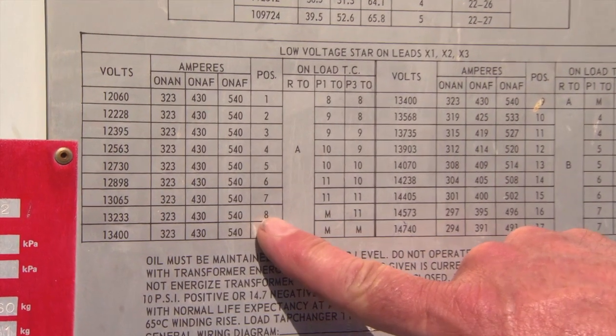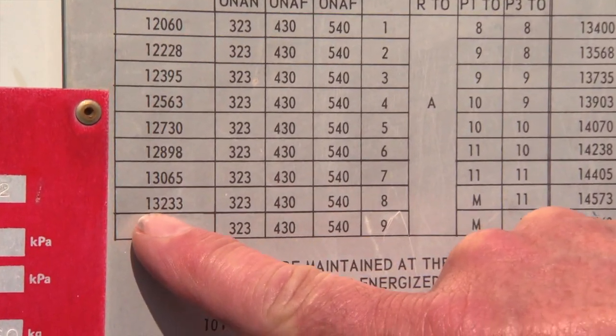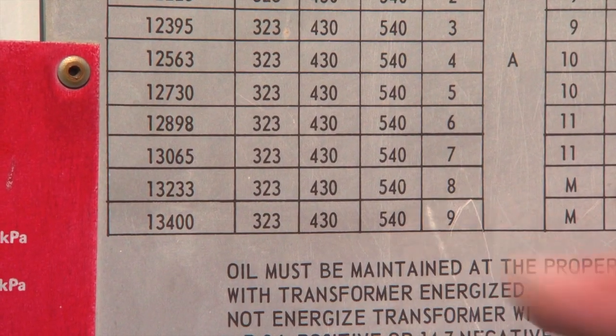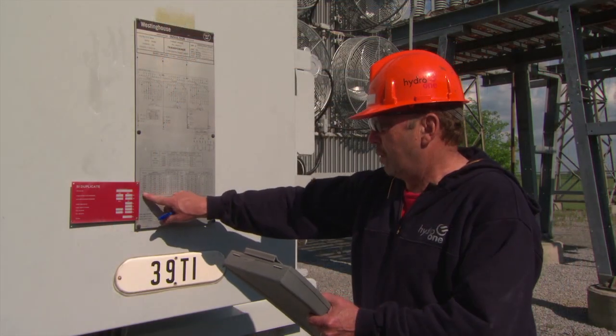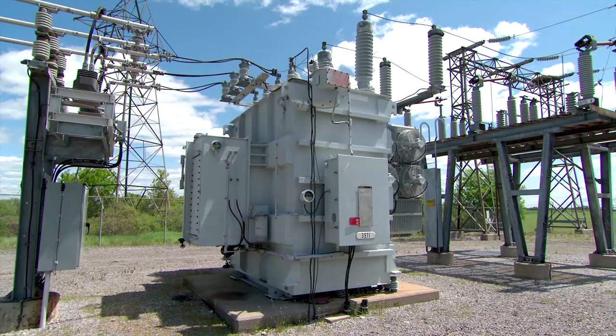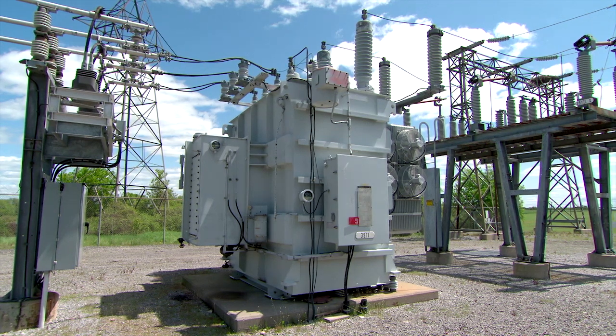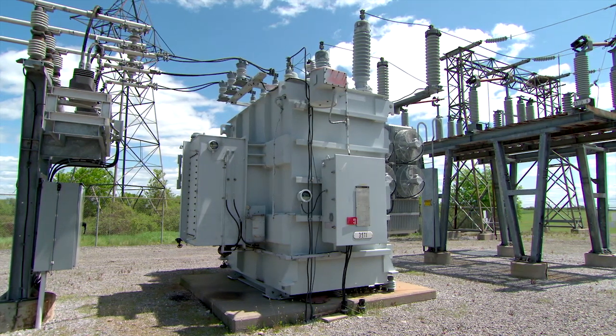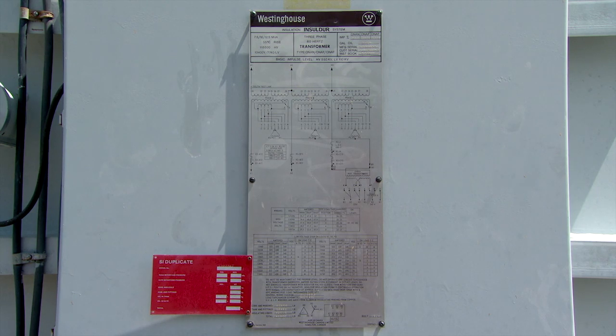13,233 volts. Check the MUS nameplate data to determine which positions the offload taps, links, or series parallel switches need to be set to match the secondary voltage of the station. The voltage on this particular mobile will be adjusted using 4 offload taps.